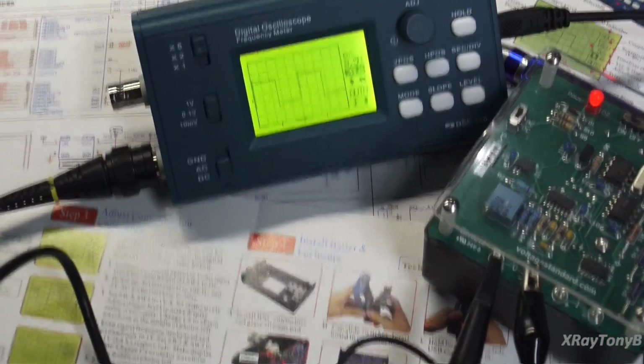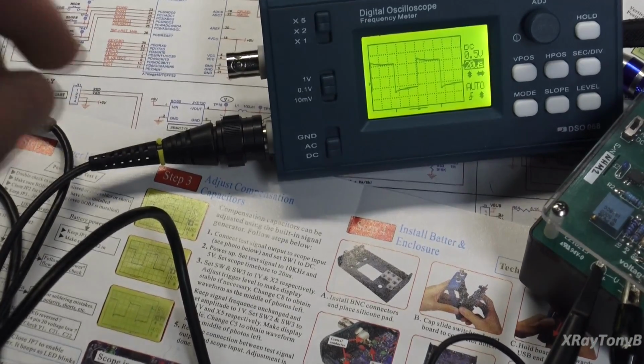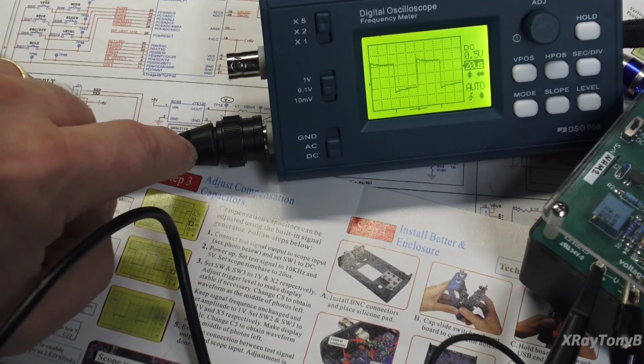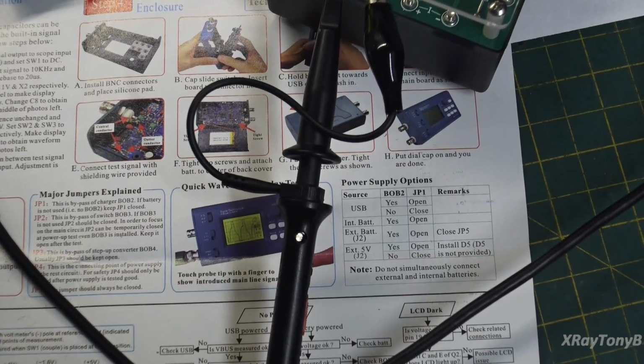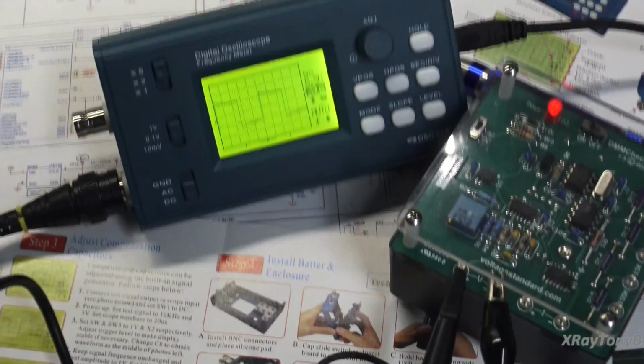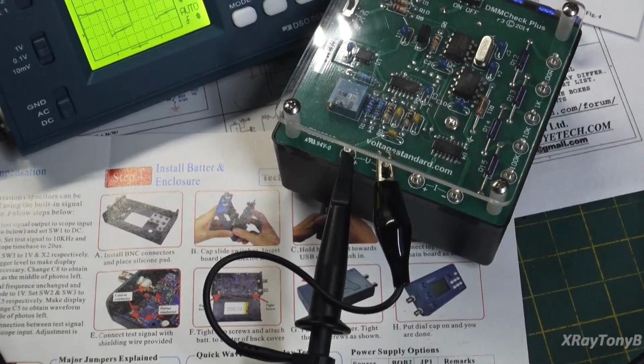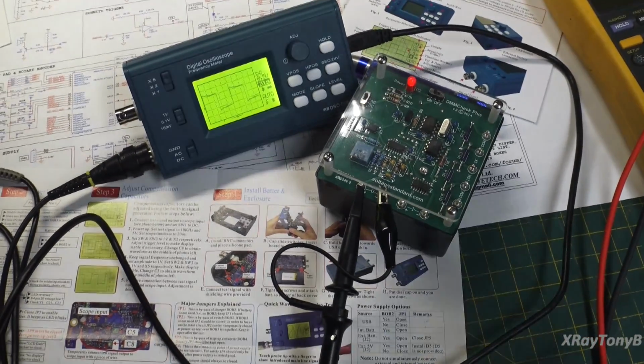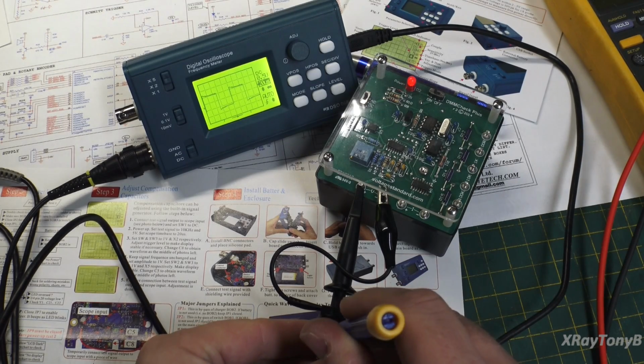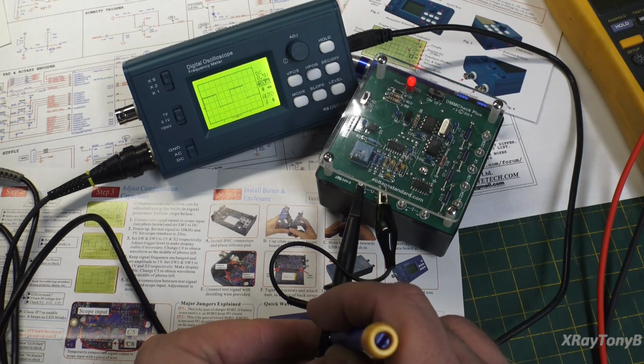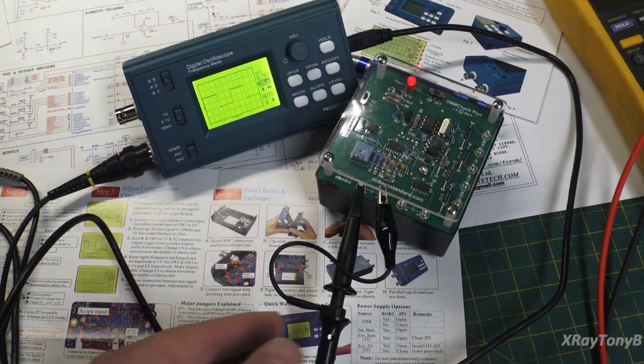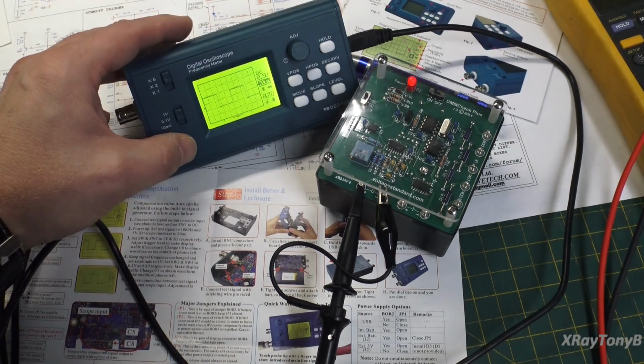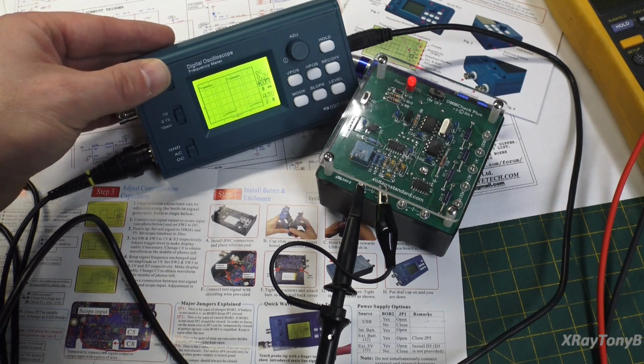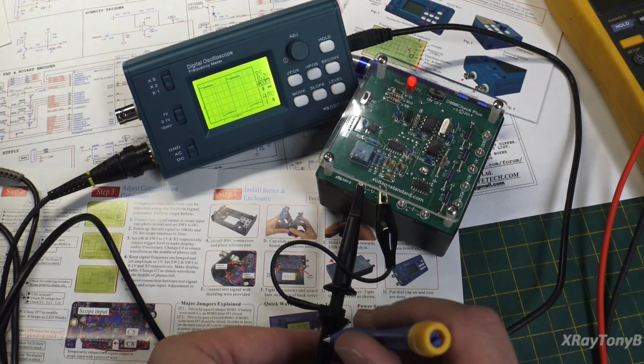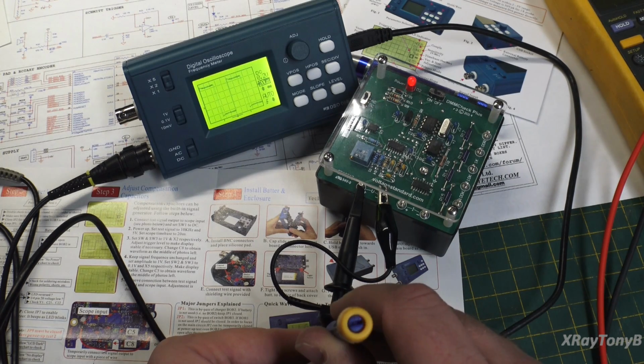Alright, I just grabbed another probe and you can see there it is. And unlike the other one, instead of the capacitance compensation adjustment being on the connector, it's actually on the probe itself on this one. So we have everything else set the same, and you can see we still have our waveform. And let's see if I can get this whole thing into the shot. There we go. And I'm going to just go ahead and adjust this. Right there. You can see we have a nice square waveform now. And now I'm going to expand it a little bit and see if we can get it even a little bit closer. And that's about all we're going to get. And you can see there it is.